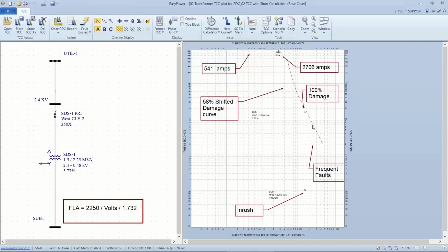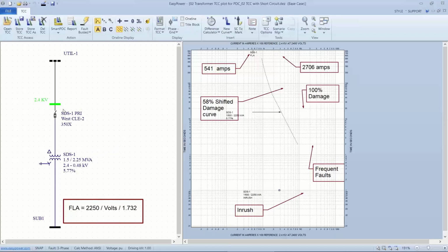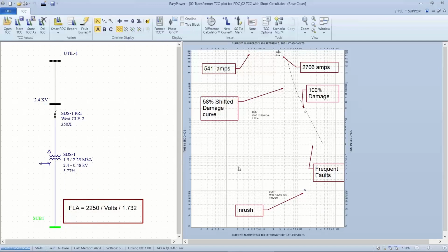So the 100% damage curve is calculated, and if we so desire, we could look at everything with reference to the 2.4 kilovolt voltage by right-clicking in EasyPower and setting the reference for TCC scaling on this bus, and we see everything shift, in this case, to a 540 amp full load current. And now this is going to be based on the 2.4 kilovolts, but we still have the same 100% curve. It's just shifted to the left. I'm going to go ahead and put it back to the 480 volt reference.